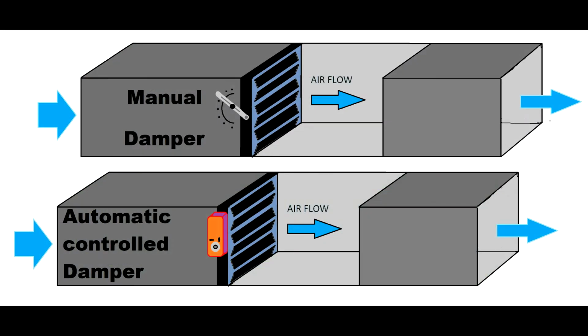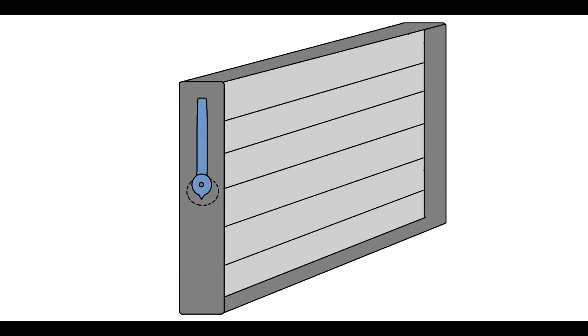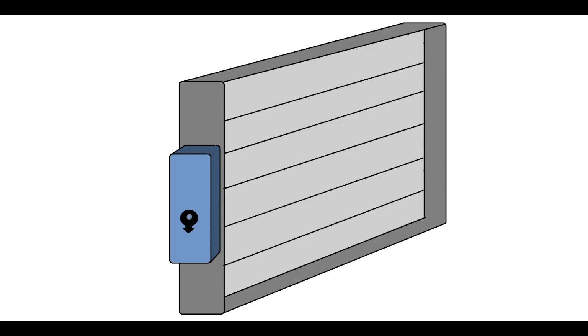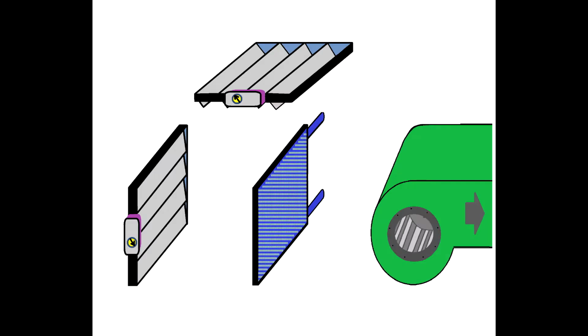To direct the airflow, we use dampers. Dampers could be manually controlled, like you see in this video, and obviously you will not do this with the damper, otherwise you'll ruin it. I just want to show you how it's working. Or they can be automatic, driven by an actuator. Going further, we'll observe here that a damper is not necessarily 0 and 100%.